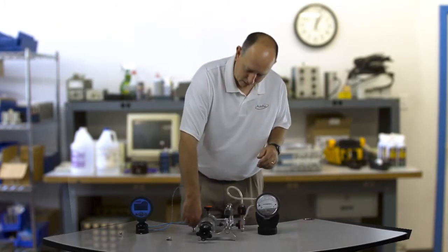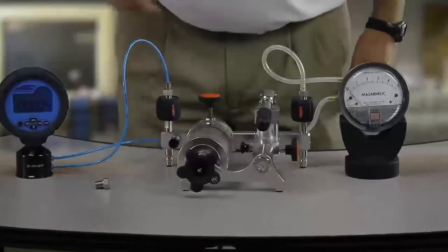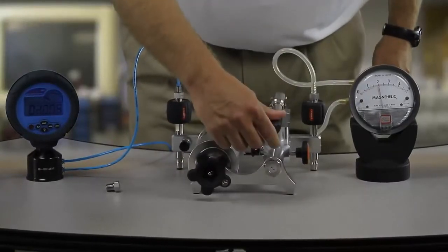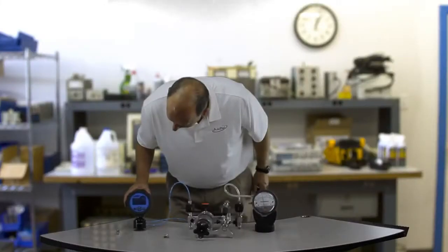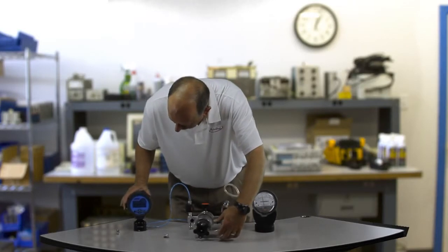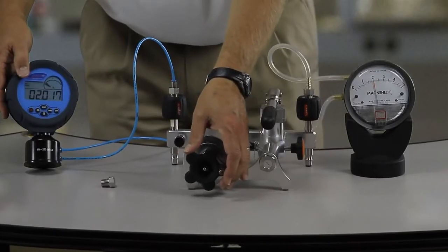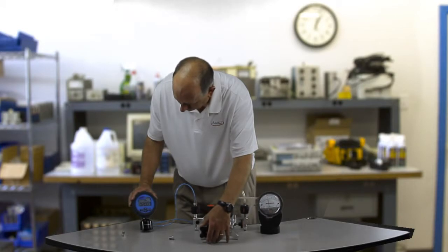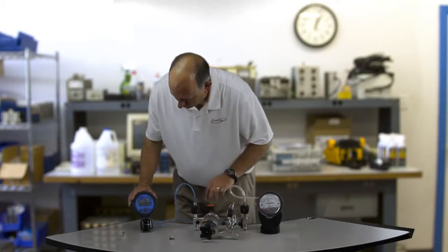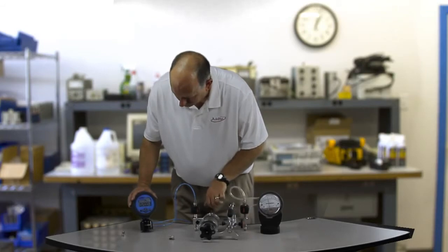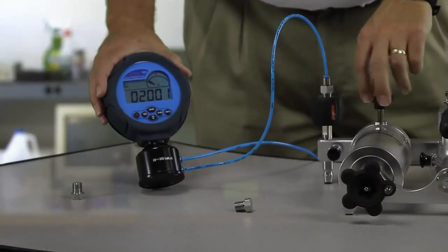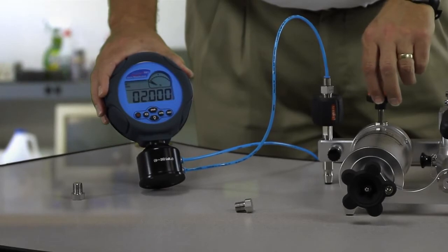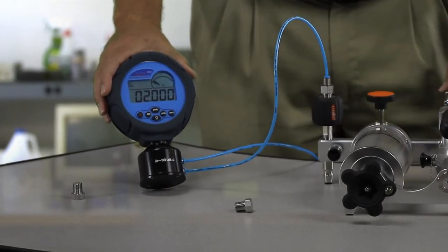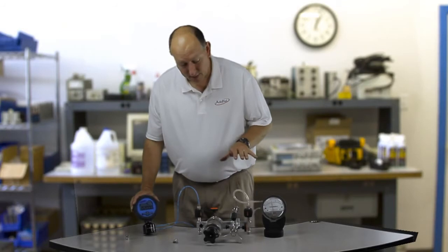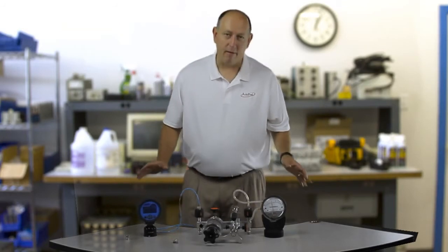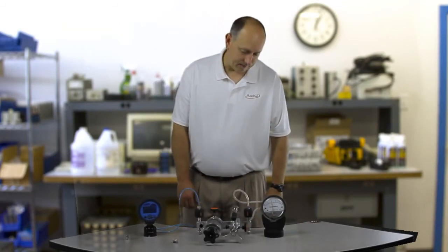Let's close my vent here. I'll use my pump to start with and get it up close to 2 inches of water - looks like I went a little bit over. Here's my reference, I'm at 2.076. Now I'm going to dial in the third digit. I've got to 2.003, and using my fine adjust here: 002, 001, 2.000. That is remarkable.